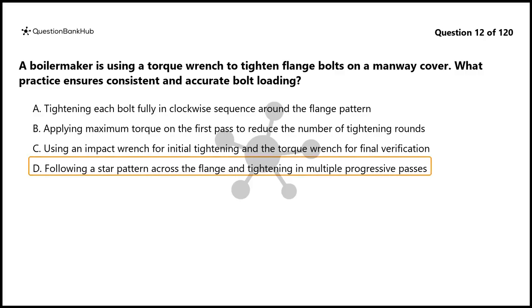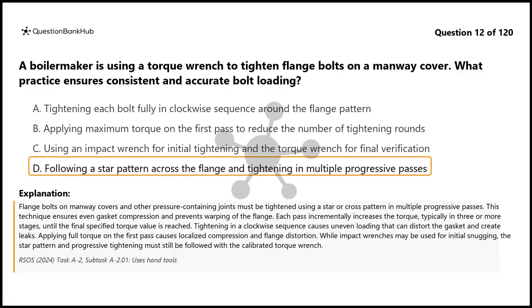The correct answer is D. Flange bolts on manway covers and other pressure-containing joints must be tightened using a star or cross pattern in multiple progressive passes. This technique ensures even gasket compression and prevents warping of the flange. Each pass incrementally increases the torque, typically in 3 or more stages, until the final specified torque value is reached.